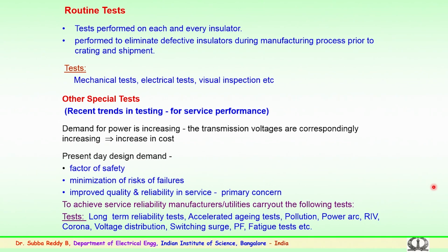The discharges should not have a higher magnitude, and specified limits have to be followed as per international norms. Next is the voltage distribution in the string for 400 or 800 kV, where the number of insulators goes on increasing. In case of 400 kV, as mentioned, we have 23 to 25 disc insulators. In case of 765 kV, we have anywhere between 35 to 40 disc insulators. So, the voltage distribution, that is from the line end to the ground end, becomes essential.